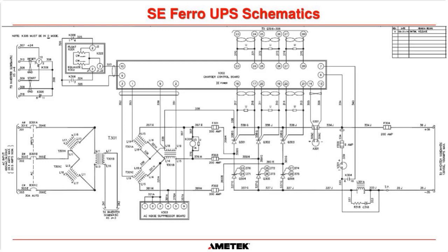Okay, and then the firing signals for the SCRs. For us to tell the SCRs when to switch on, for these top SCRs, we use these channels here out of the control board. And then to prevent the drawing getting really messy, for these bottom SCRs, we reference the terminals here, 23 and 24. So that's that terminal there and that terminal there. This one here is 25 and 26. It's cable number 372 and 373. And the same for that one there.